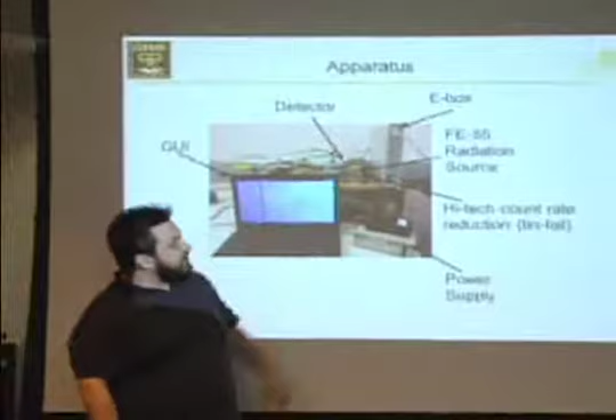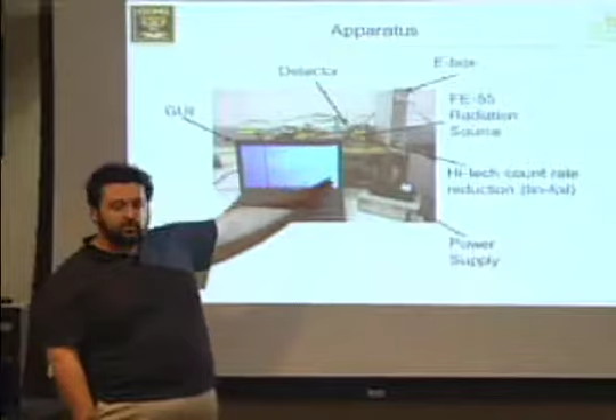In the front, we have a radiation source that's an iron-55 radiation source. Now, the count rate on iron-55 is about 6 kilohertz, and our system is not designed to handle a count rate that high. So we have a high-tech count rate reduction system, tinfoil, in front of our iron-55 source.